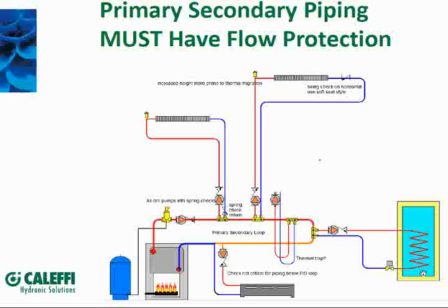One situation that can really bite you is an indirect tank off a primary loop. If that tank heats up to 140°F and the boiler shuts off but a pump is running for a call, heat can migrate out of the indirect tank back into the primary loop and up into other circuits. You really want 100% shutoff protection on indirect tanks. Some guys put a zone valve so the call for heat triggers the zone valve and the end switch turns on the pump — giving you both the check valve in the pump and the zone valve as protection.